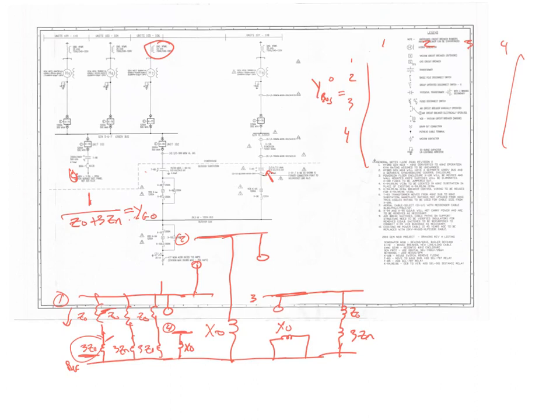So this is going to be 3YG0, right? Because I've got 3 generators connected there. And that's it. Is there anything that goes between bus 1 and 2? No. Anything between bus 2 and 4? Nope. So these are all zeros. Because I've got 3 of them. It's only 3 times that because it's this element here plus this one plus this one. Those 3 added together. Question?